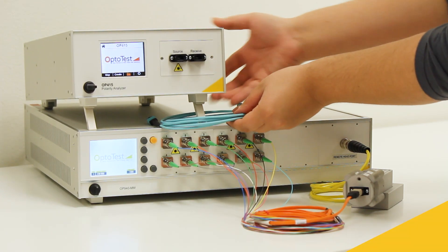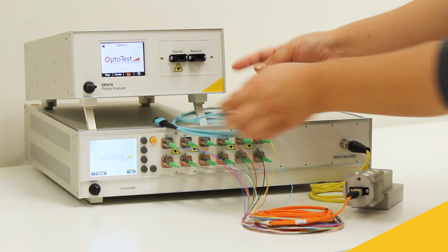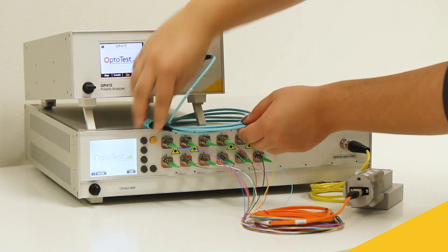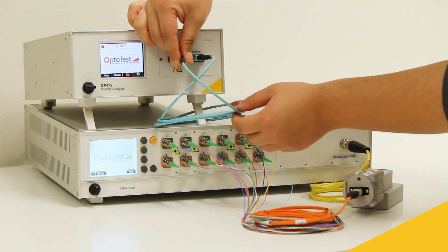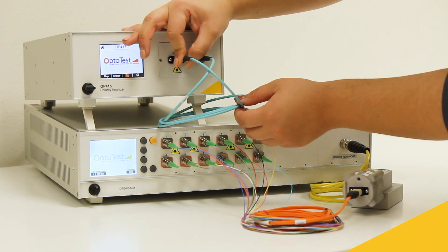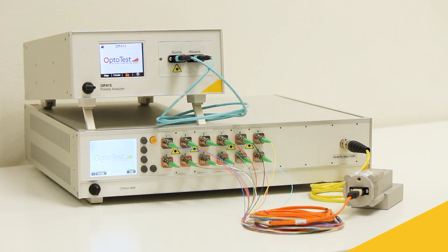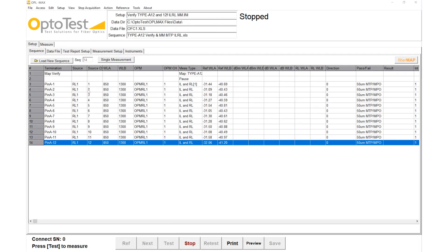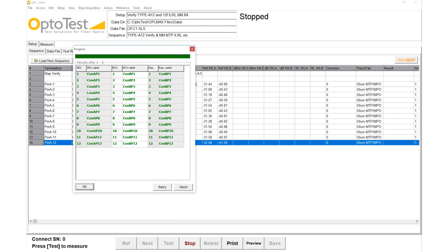The DUT is connected to the OP415 for the polarity test. This window shows that the mapping of the fibers in the cable matches the Type A mapping it was tested against.